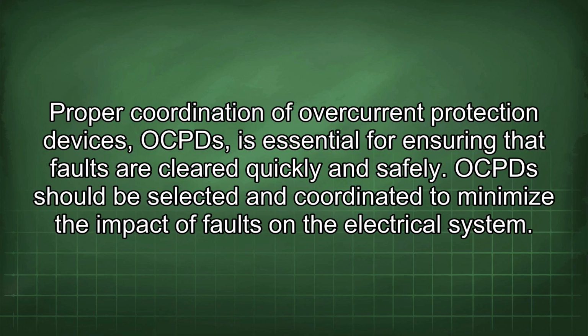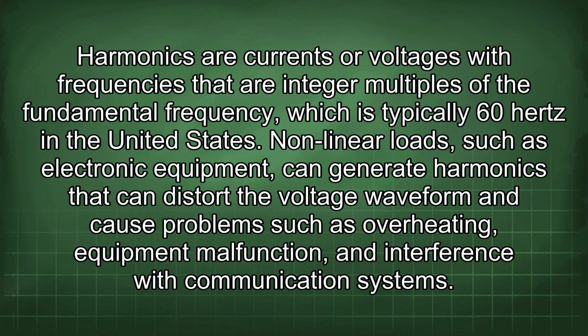Proper coordination of overcurrent protection devices, OCPDs, is essential for ensuring that faults are cleared quickly and safely. OCPDs should be selected and coordinated to minimize the impact of faults on the electrical system. Harmonics are currents or voltages with frequencies that are integer multiples of the fundamental frequency, which is typically 60 Hz in the United States. Nonlinear loads, such as electronic equipment, can generate harmonics that can distort the voltage waveform and cause problems such as overheating, equipment malfunction, and interference with communication systems.